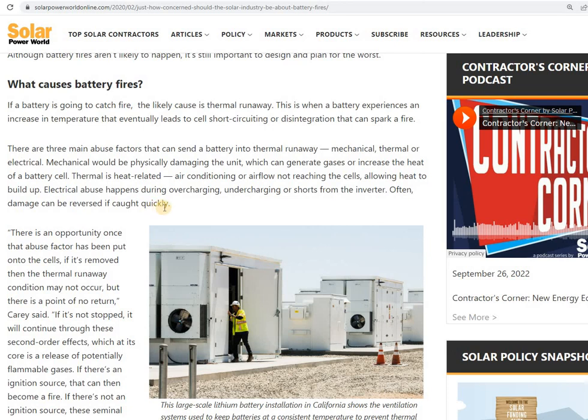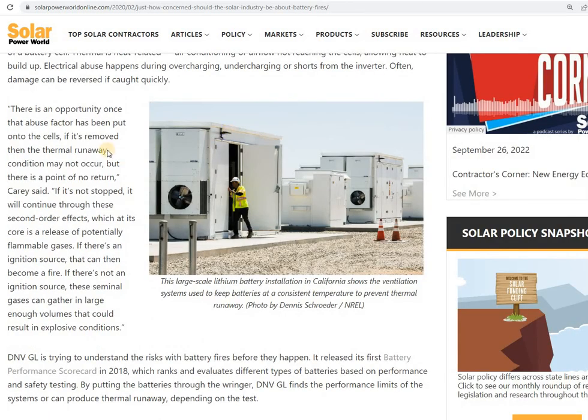Often the damage can be reversed if caught quickly. There is an opportunity once the abuse factor has been put onto the cells. If it's removed, the thermal runaway condition may not occur, but there is a point of no return. If not stopped, it will continue through second order effects, which at its core is a release of potentially flammable gases.